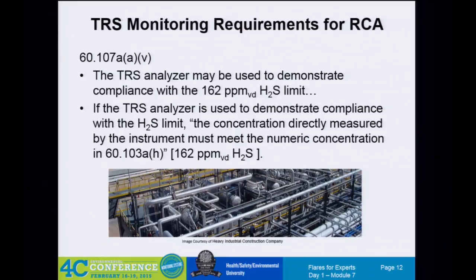Yeah, which gets back to the whole point that a lot of these test methods and RCA requirements were all written for things like boilers, heaters, something that's running at a nice steady rate with a nice consistent fuel supply, so you can get these measurements to know how it's performing. The flare system is anything but. So I think the problem we see most people dealing with is how do we force-fit these methods that were designed for equipment that doesn't work at all like what it's on. And I think that's going to be a lot of the challenges.